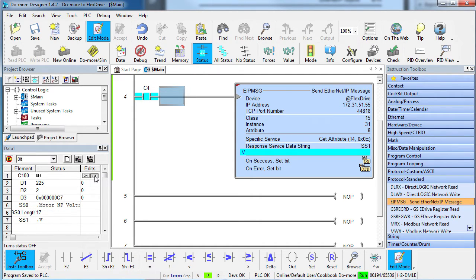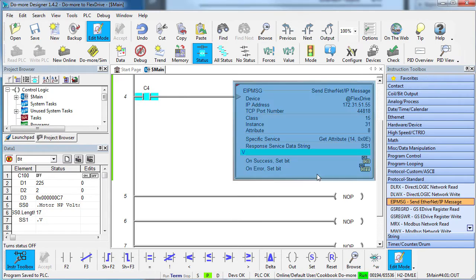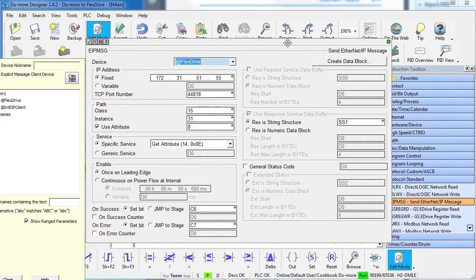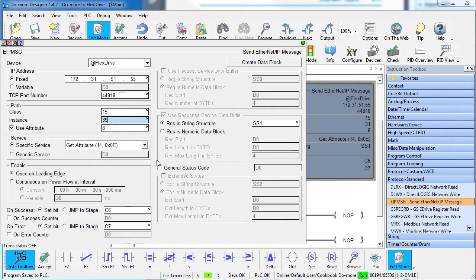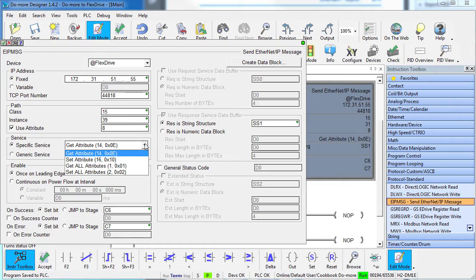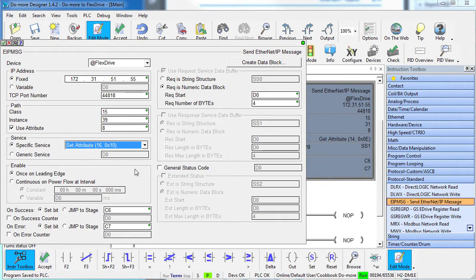What if we wanted to do all of this for the acceleration parameter? Same thing, right? Except now we want parameter or instance number 39. What if you wanted to SET a parameter instead of GET one? Well, the SET service code is 10 hex or 16 decimal. Everything else pretty much the same.